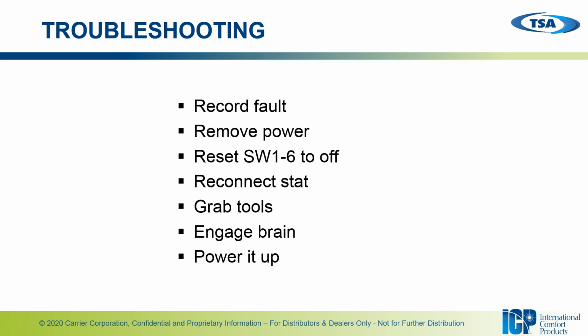So at the end of your self-test, you want to record the fault. And I will forewarn you, those LEDs and fault codes, the control board runs through them very quickly, so you have to pay close attention. All right, record your fault, remove the power, and then reset the dip switch back to the off position, reconnect your stat, grab your tools, engage your brain, and power the unit back up. We say engage your brain because you may have to think outside the box when it comes to blower motor issues.